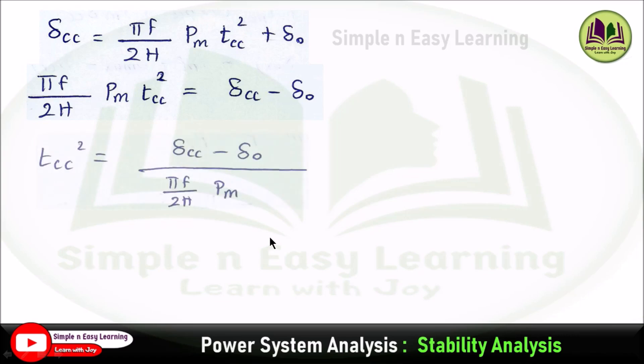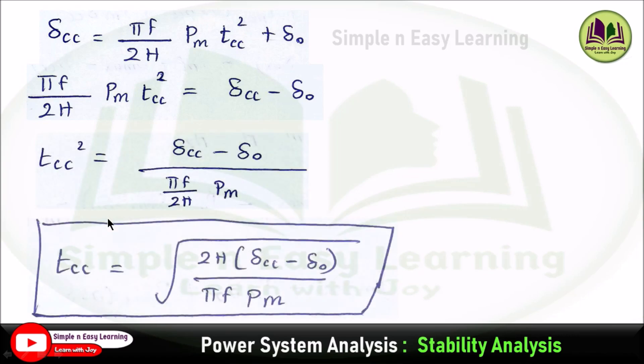Therefore, t_cc equals the square root of 2h times (delta_cc minus delta_0) divided by pi f times P_m. This is the critical clearing time formula for a single machine infinite bus system.